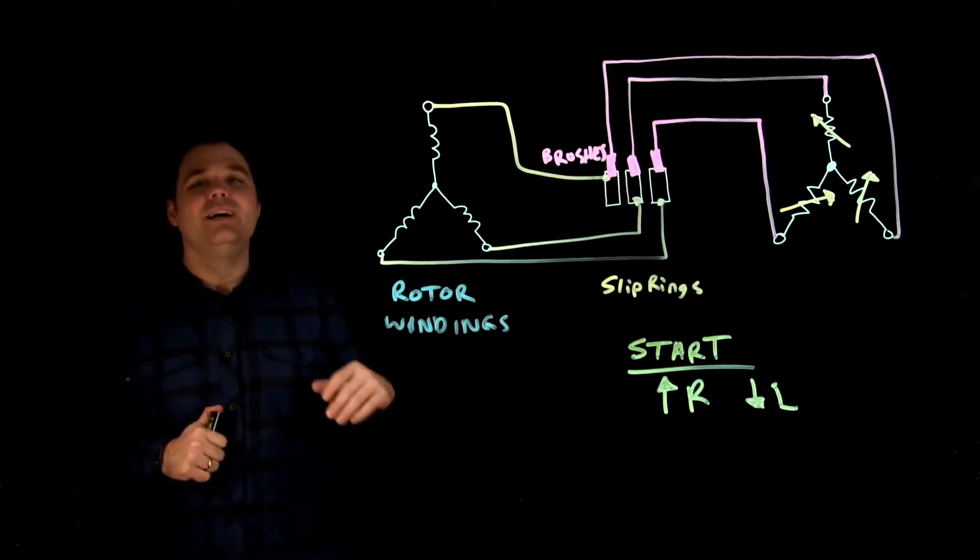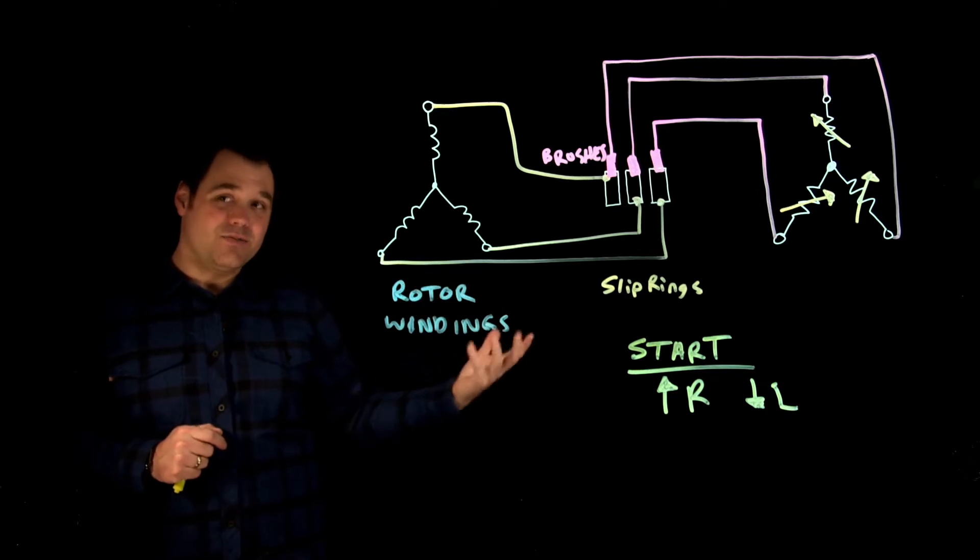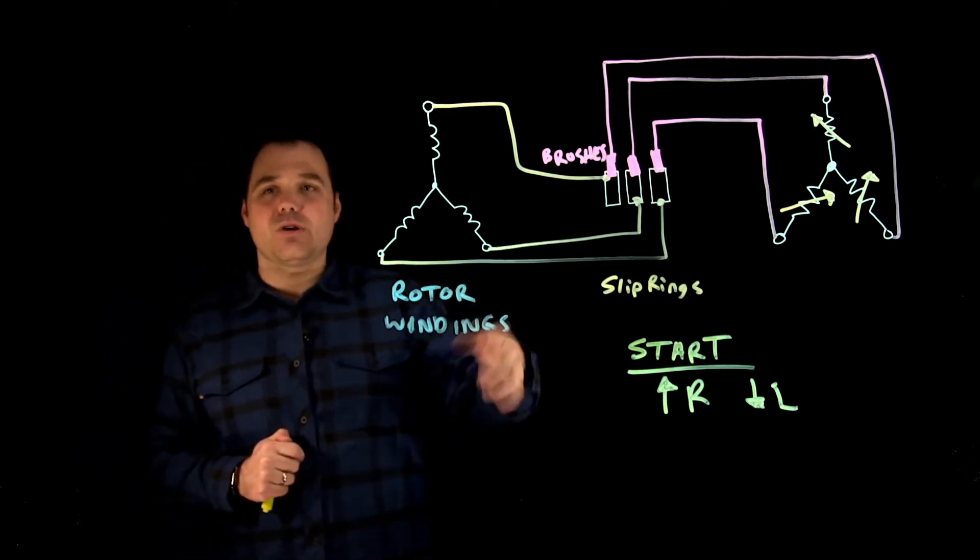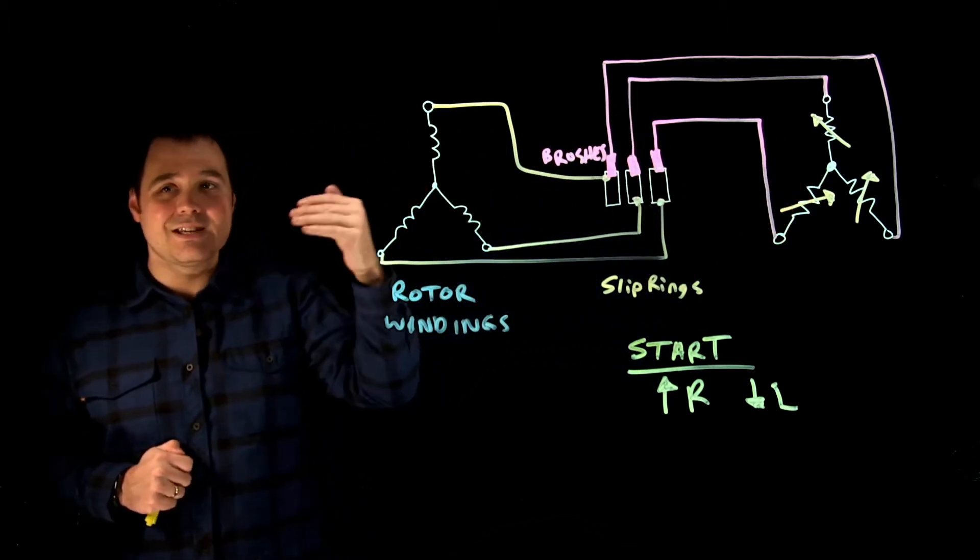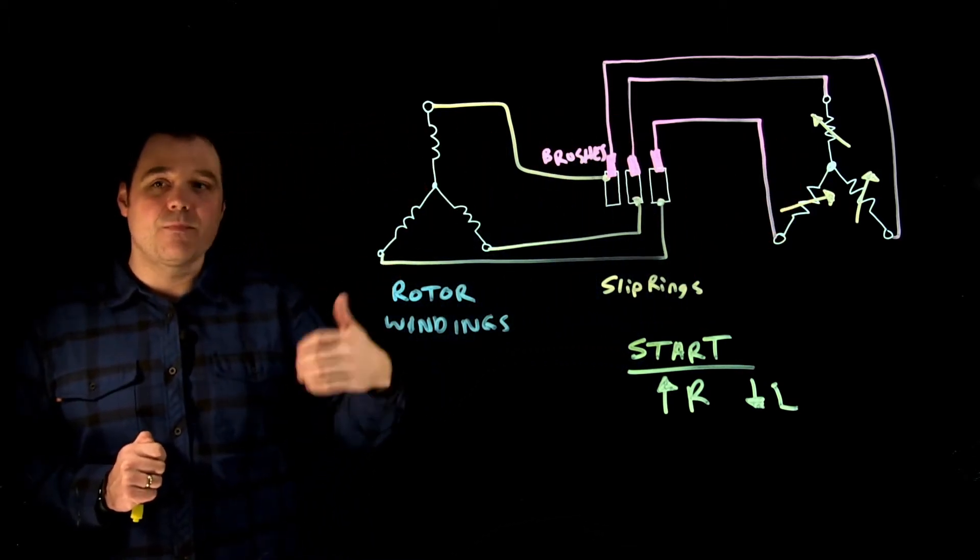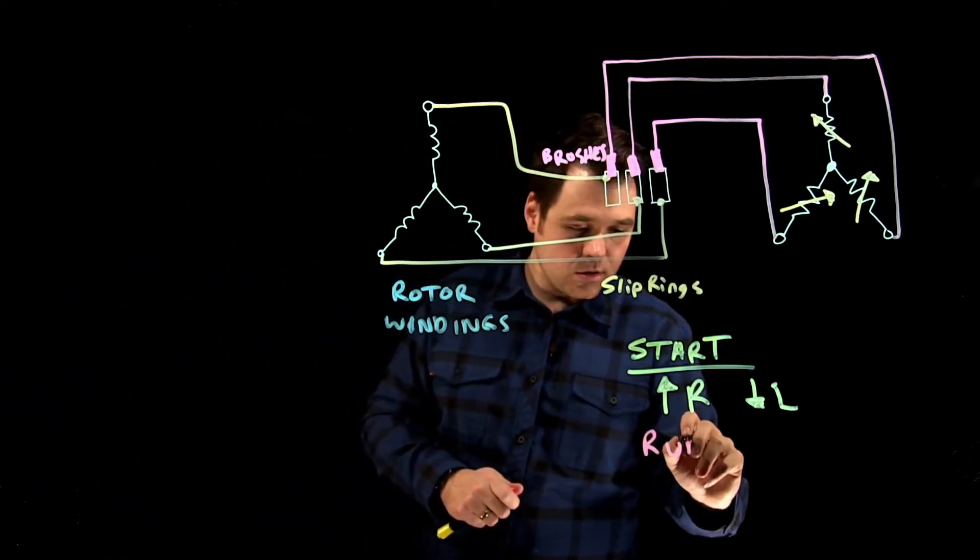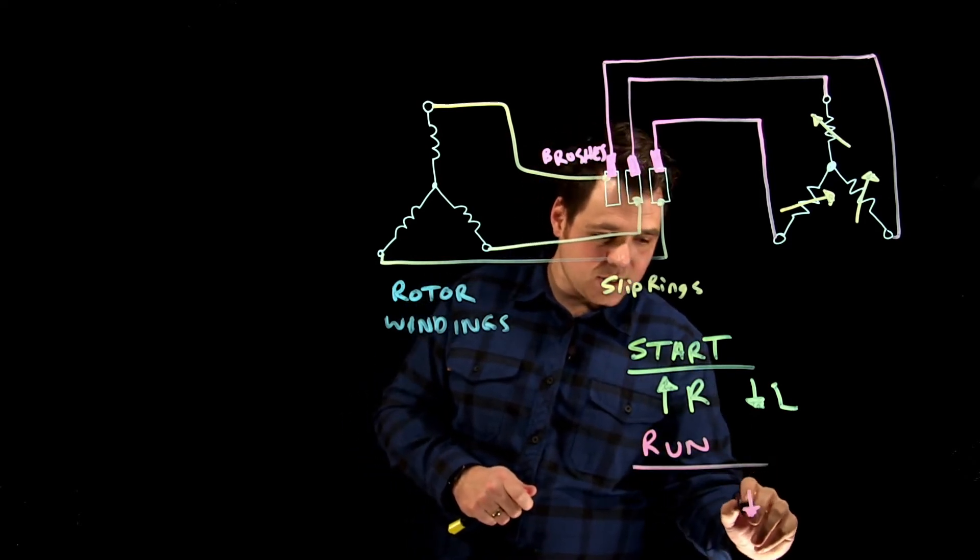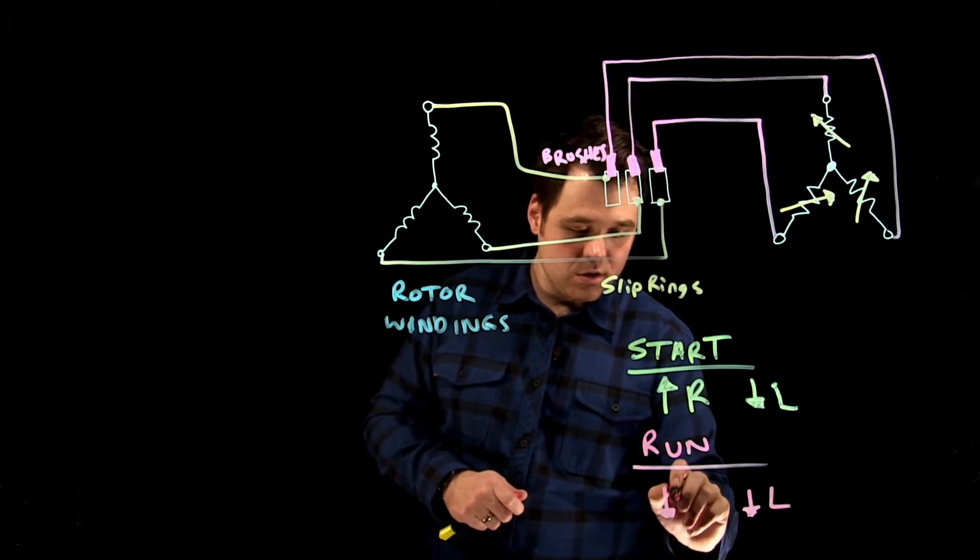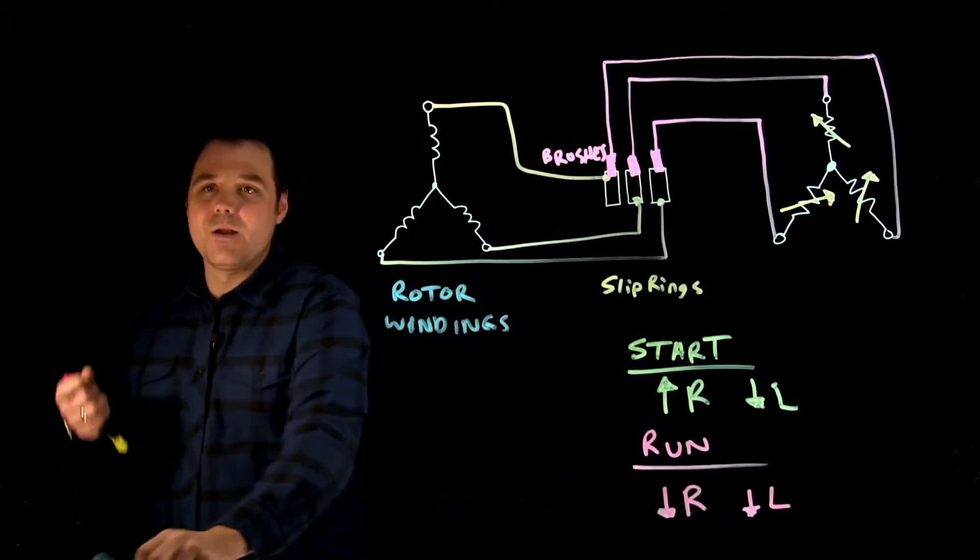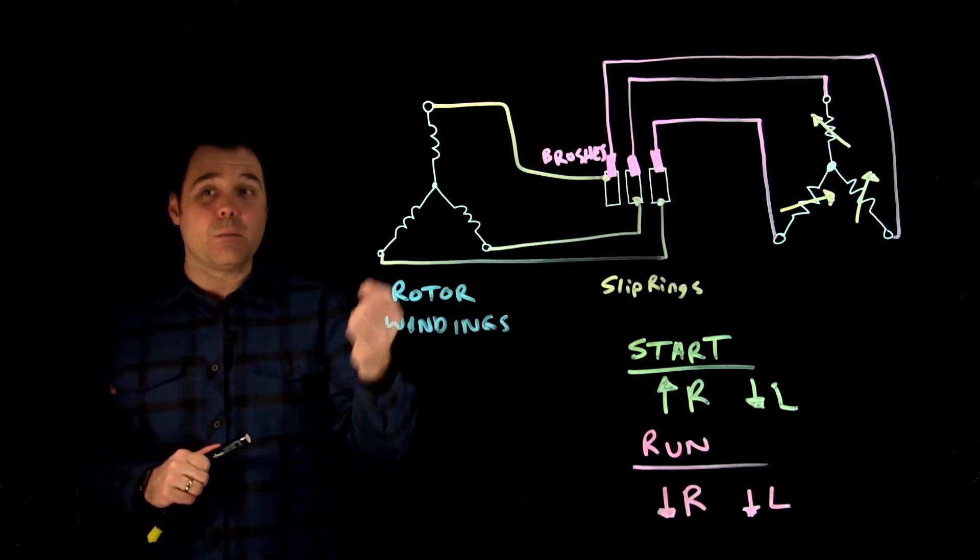The problem normally with the D is that it's very inefficient at later on because of that high resistance. But as this motor starts to spin, what we do is we start to adjust that resistance and we lower the resistance as the motor starts spinning. So as we lower the resistance, what happens is at run, we still have a low inductance. But now we have a low resistance.